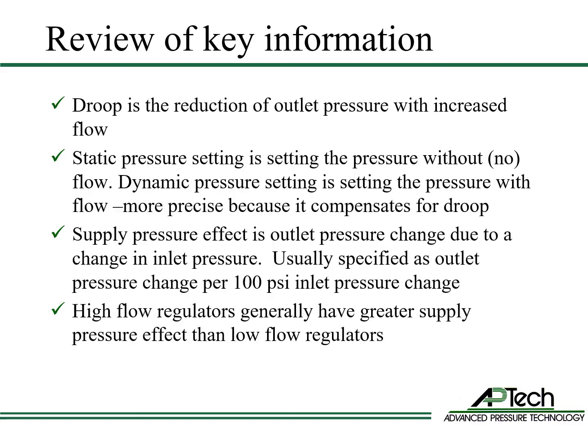Now let's review the key information about droop, flow curves, setting outlet pressure, and the supply pressure effect in gas regulators. Droop is the reduction of outlet pressure with increased flow. Static pressure setting is setting the pressure without flow. Dynamic pressure setting is setting the pressure with flow — this method is more precise because it compensates for droop. Supply pressure effect is outlet pressure change due to a change in inlet pressure, usually specified as outlet pressure change per 100 psi inlet pressure change. High flow regulators generally have more supply pressure effect than low flow regulators.